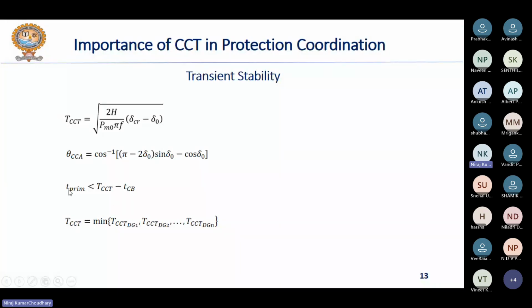Here in the third equation, you can see that T_prim is the time of operation of the primary relay, right? We have seen in the previous few diagrams that there was some primary relay in the system and some backup relay in the system. So on the occurrence of a fault, the time of operation of the primary relay plus the time of operation of the circuit breaker should always be less than the critical clearing time, T_CCT. Otherwise, your system may become unstable. That's why I mentioned that while formulating your relay coordination scheme, the constraint of CCT, that is critical clearing time, should always be incorporated in the system, right?